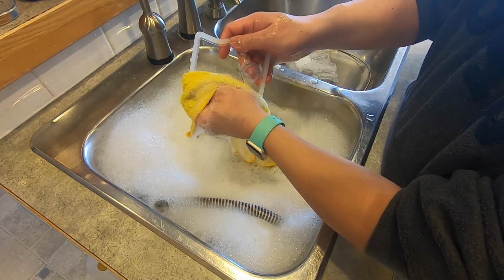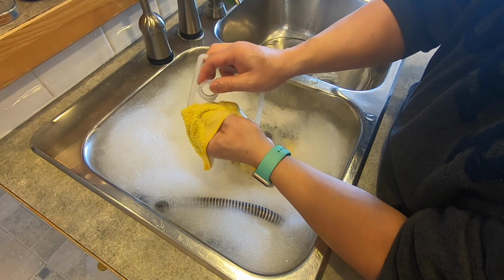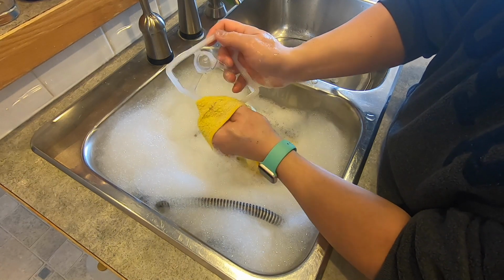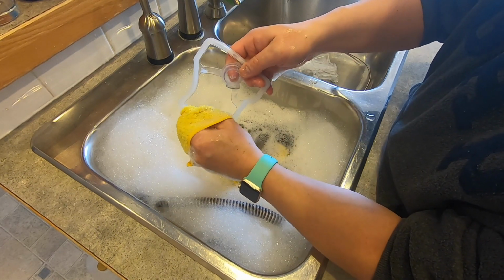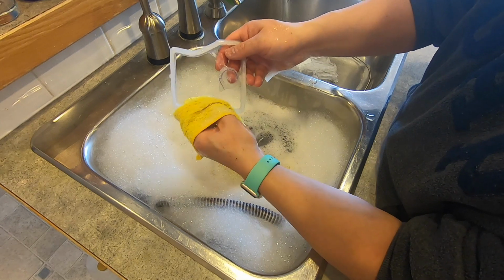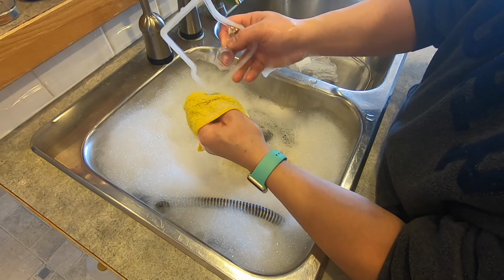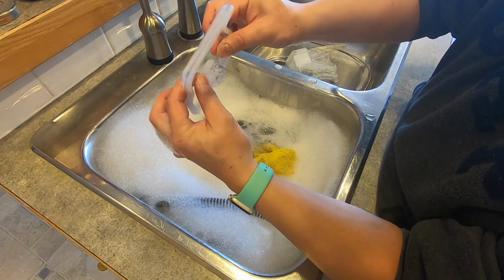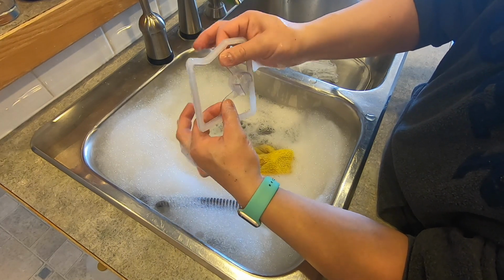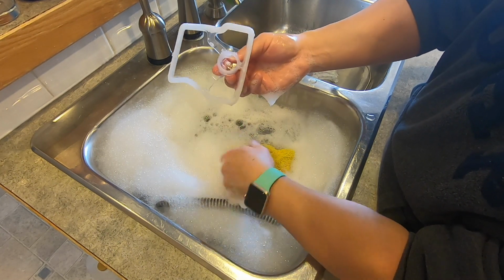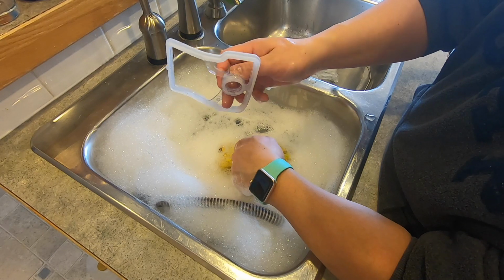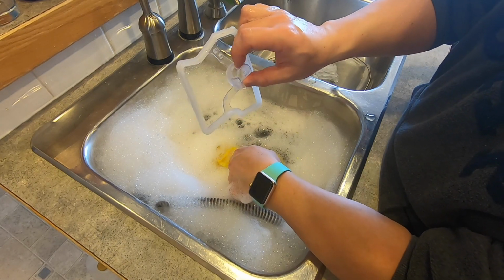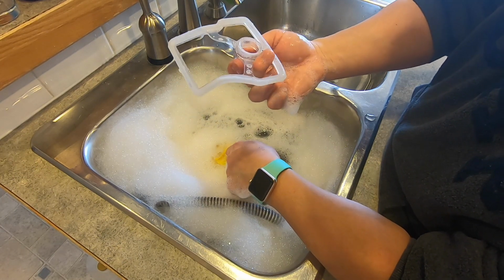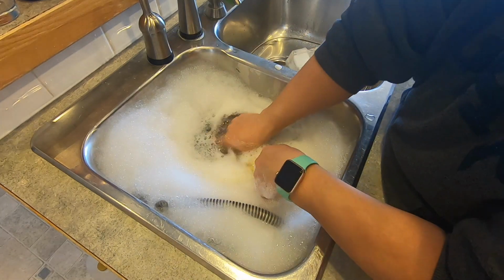You can clean the gasket and just massage the seal in a very delicate manner. You want to be very careful with the ResMed seals — I don't know if other brands have the same issue — but the ResMed gasket here is very thin and very delicate, so it doesn't take much to snap one of these things. And my understanding is that you cannot buy just this gasket should you break it from ResMed; you actually have to buy the entire water tub assembly.